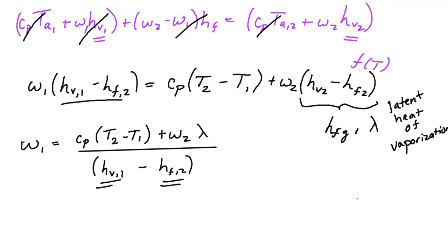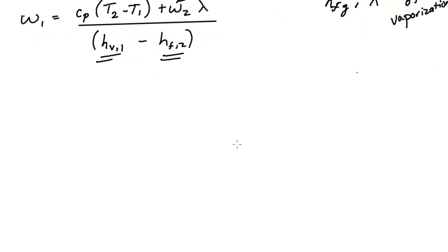And we also know that this was at a relative humidity of 100%. And we have a relationship with pressure for absolute humidity ratio. And we knew that to be 0.622. And this is the partial pressure of the vapor at saturation divided by total pressure minus that same pressure. And so if we know we're at a given temperature, we can go back to that table I just had and look up the saturated pressure, and we can get this value.